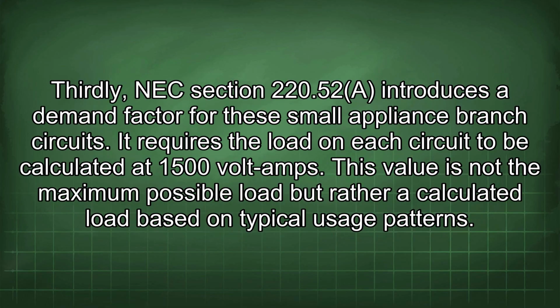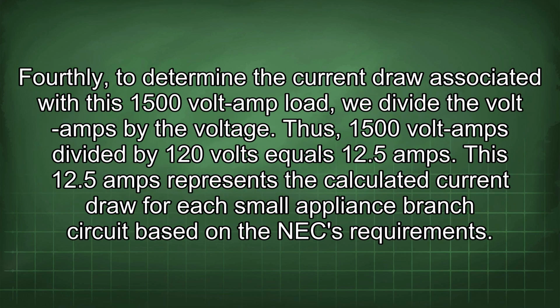Thirdly, NEC section 220.52 introduces a demand factor for these small appliance branch circuits. It requires the load on each circuit to be calculated at 1500 volt amps. This value is not the maximum possible load, but rather a calculated load based on typical usage patterns. Fourthly, to determine the current draw associated with this 1500 volt amp load, we divide the volt amps by the voltage. Thus, 1500 volt amps divided by 120 volts equals 12.5 amps. This 12.5 amps represents the calculated current draw for each small appliance branch circuit based on the NEC requirements.